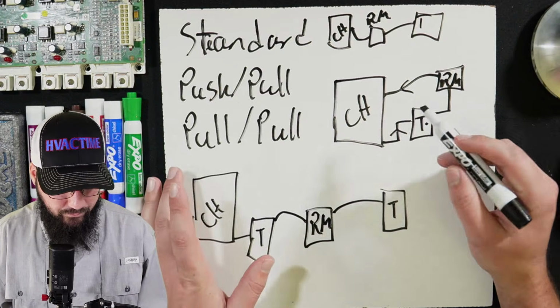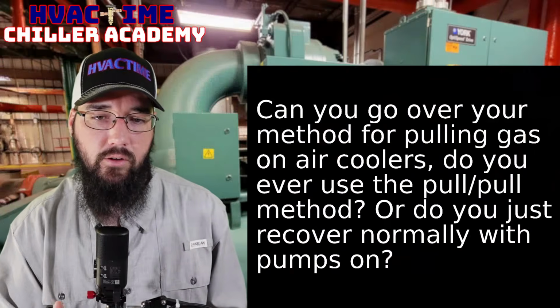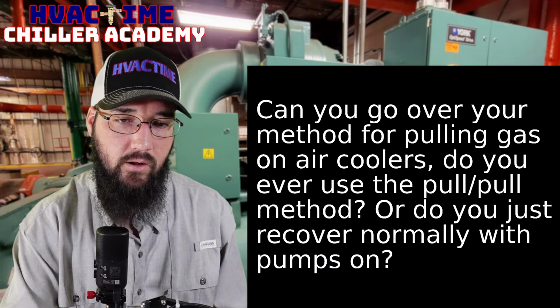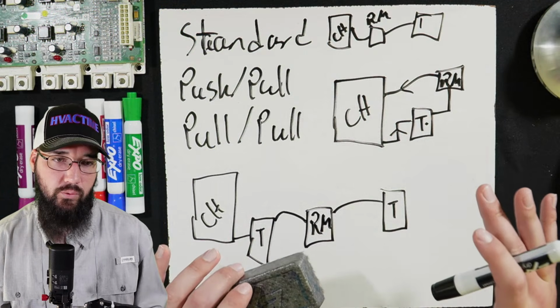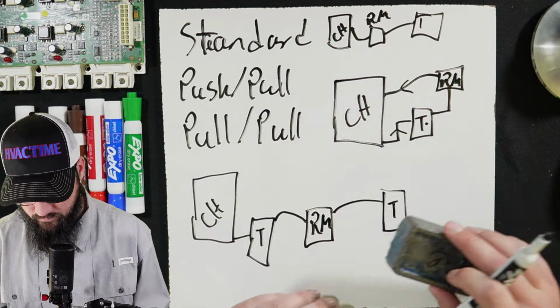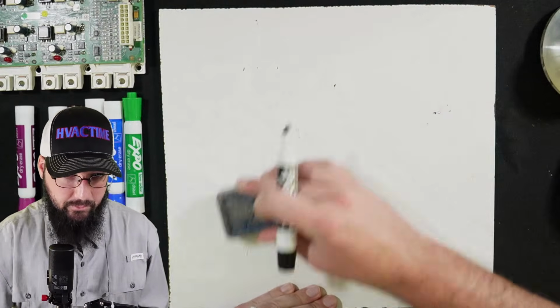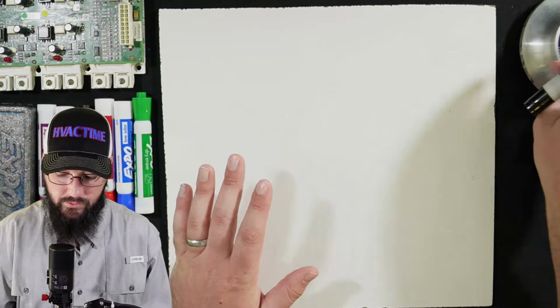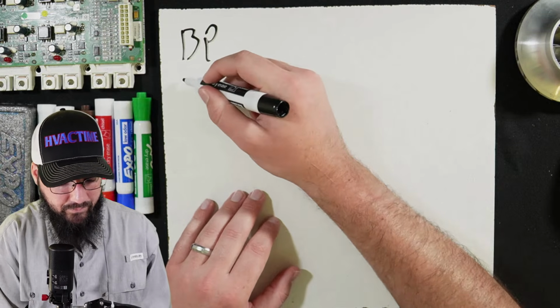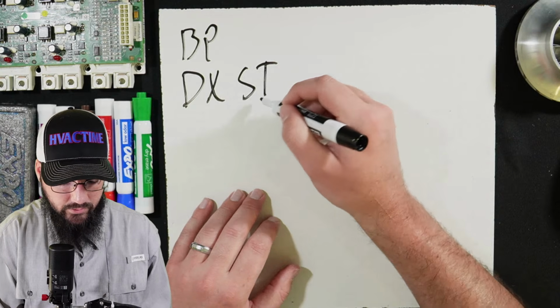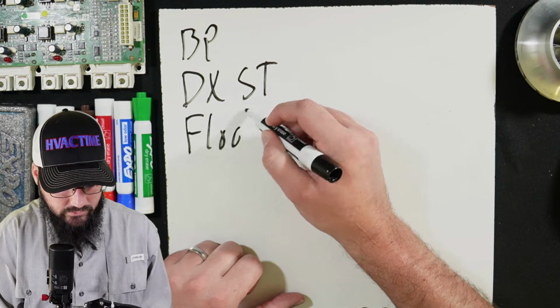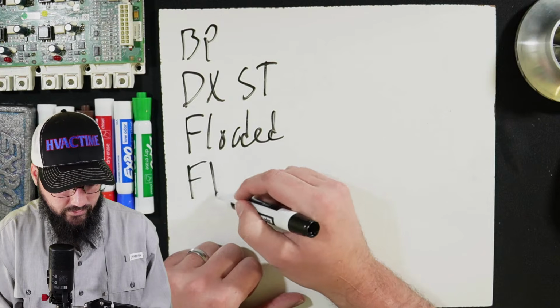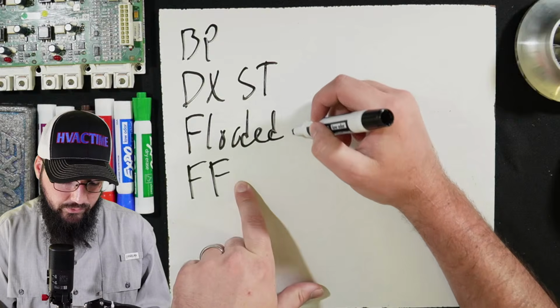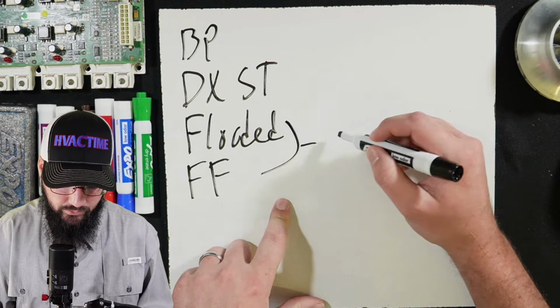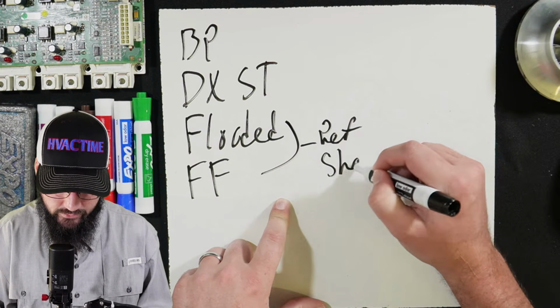Just saying. So now we understand what we're discussing. When we talk about whether you ever use the pull-pull method on an air-cooled chiller, we're clear on what methods we're describing: standard, push-pull, and pull-pull. Now, I said that the evaporator matters a lot. There are four main evaporators we should expect to see. We've got braze plate, BP. We have the DX shell and tube, ST. Then we have a flooded, which is also a shell and tube. Then we have a falling film, FF. For both of these, the refrigerant is on the outside of the tubes, so the refrigerant is on the shell side.